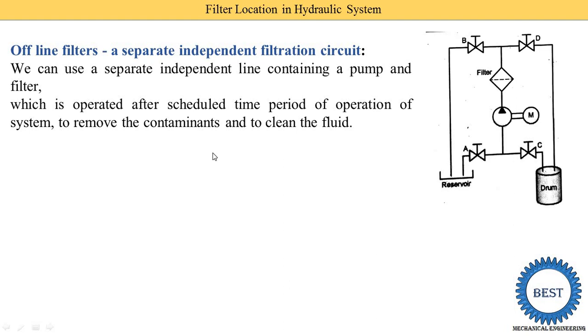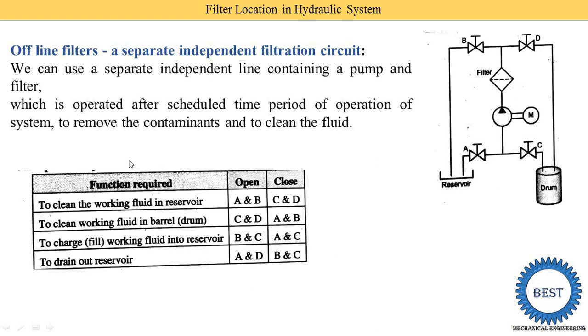Case 1: to clean the working fluid in the reservoir. Oil is taken from the reservoir by opening valve A. Valve C is closed so oil does not go to the drum. Oil flows from valve A to the pump, then through the filter where contamination is removed. After the filter, valve B is opened and valve D is closed, so the cleaned oil is supplied back to the reservoir.